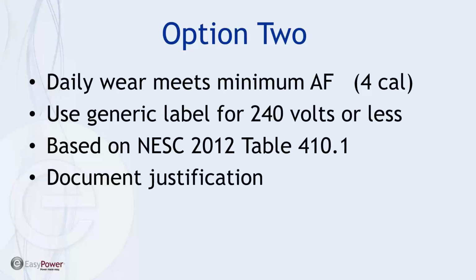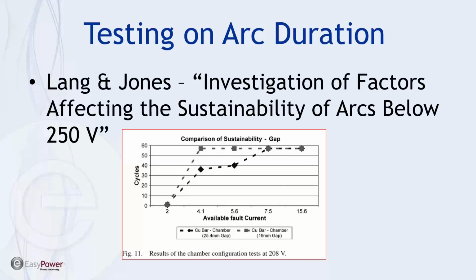So you'd want to make sure you document the justification. So that's option 2. Now, I mentioned there was additional testing on arc duration, and here's just an example of the typical results, and that is on low voltage, and again, this is 250 volts or less, that arc could be established, but it would not self-sustain with available fault current less than 4 kiloamps. And so the 2-second limitation is fairly conservative.